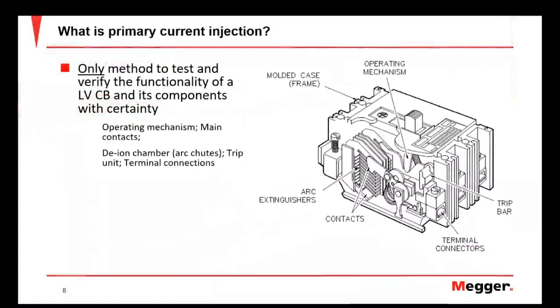So what is primary current injection? Primary current injection is the only method we can effectively use to do a functional test on circuit breakers and some other components. It's the only method we can use to verify that all the mechanisms within a circuit breaker are going to operate as intended whenever it's in use in a real-world scenario.